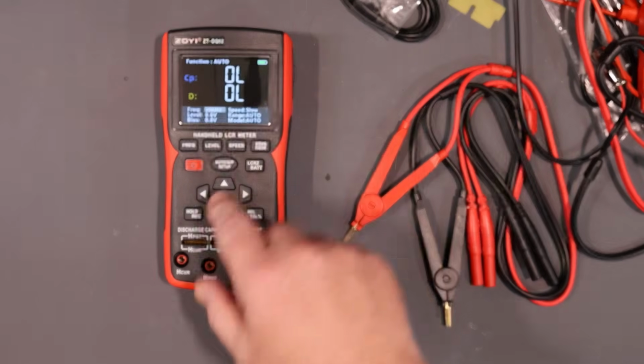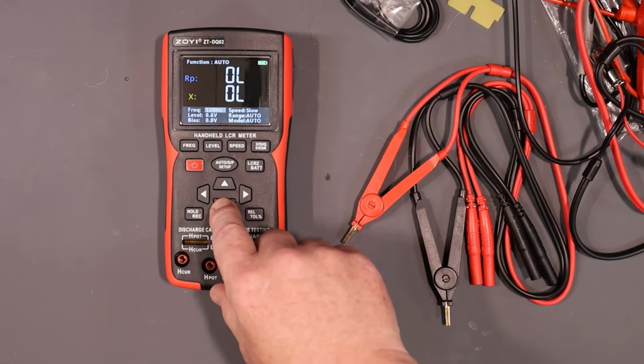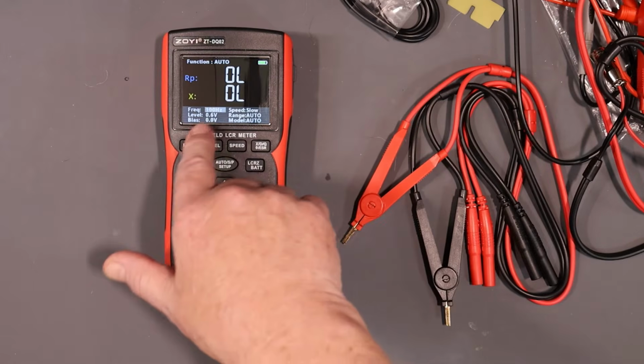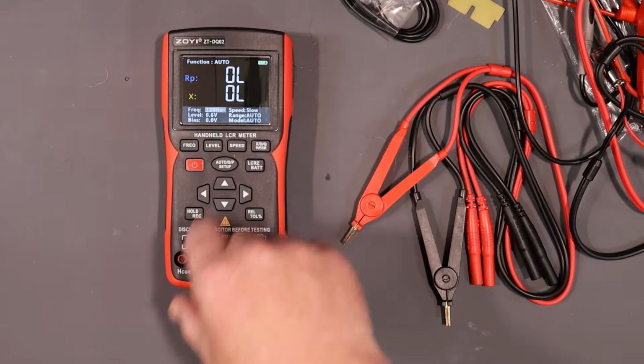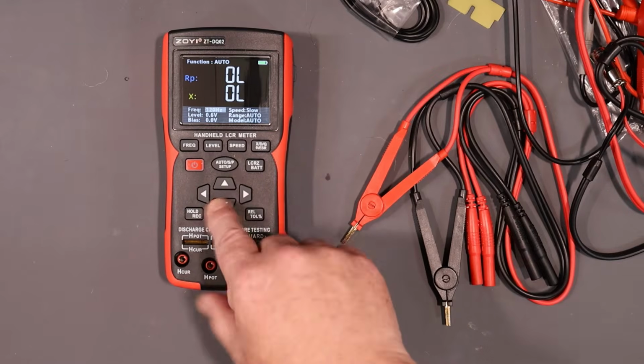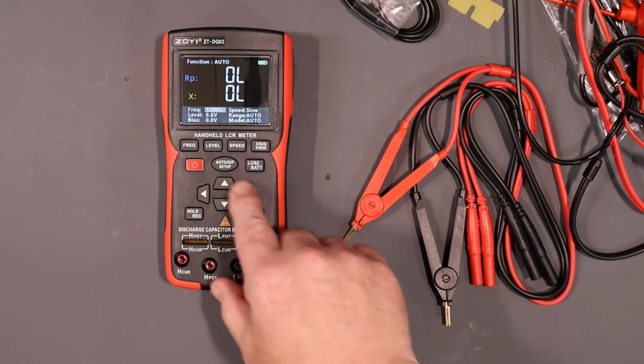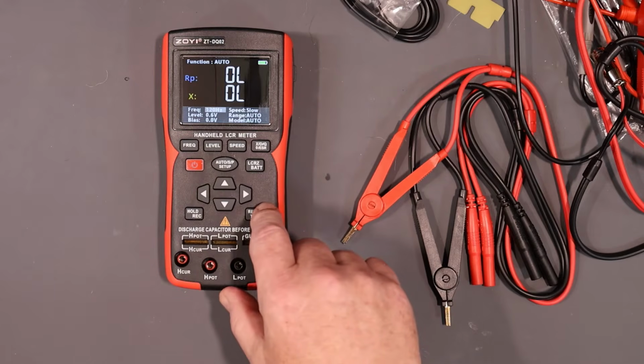So if you're going to be using the capacitor at 10 kilohertz, test it at 10 kilohertz. If you're going to be using the capacitor, like for a filter capacitor here in North America, you want to test it at 120 hertz. Or if you're in Europe, you want to test it at 100 hertz. And that's why they have those two specific ones there too.